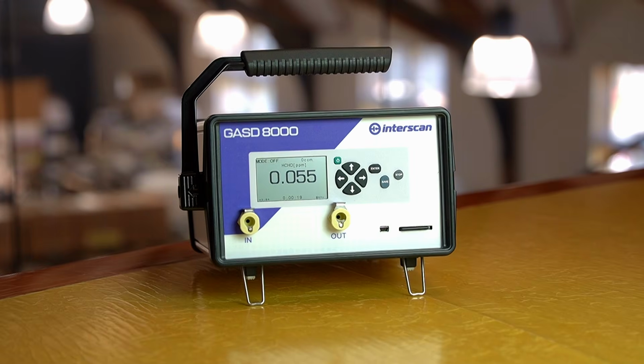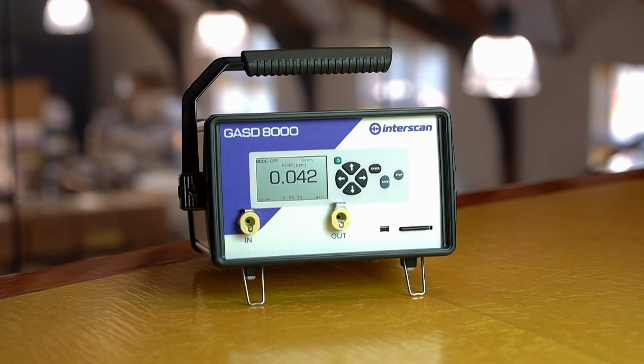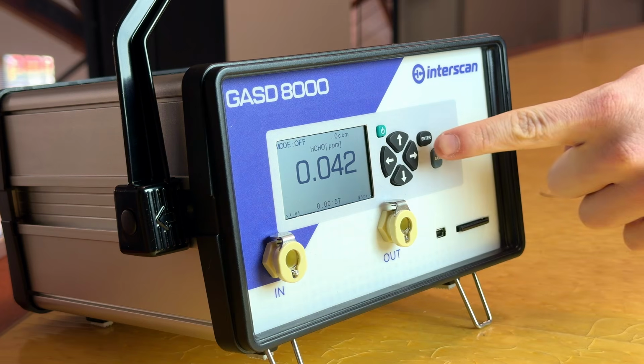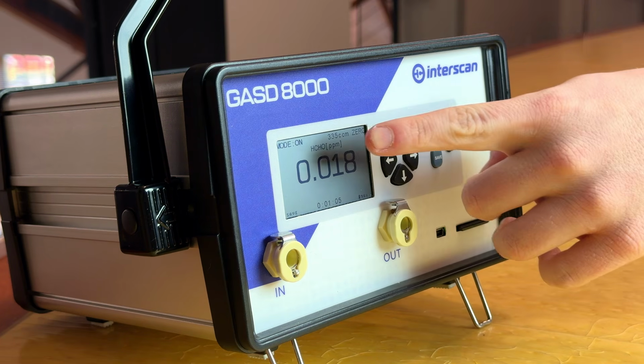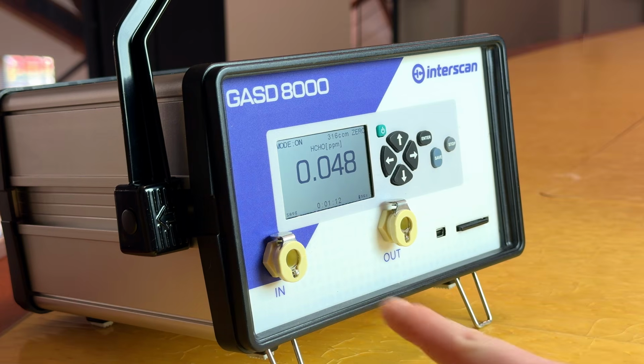When stabilization is complete, the instrument enters off mode. In this mode, the pump is off and the analyzer is idle. Press Enter to switch to on mode and begin active sampling. If you listen closely, you can hear the pump start.